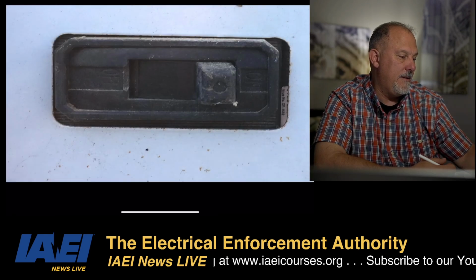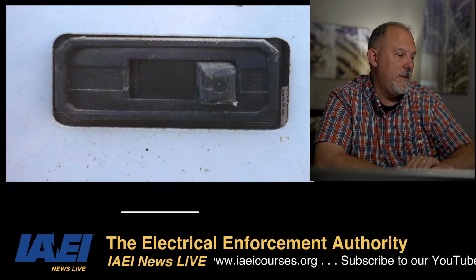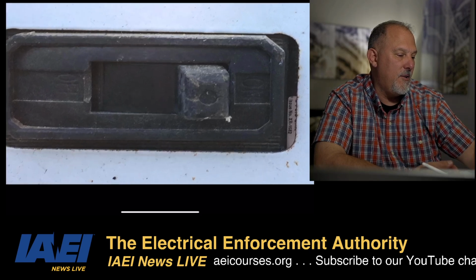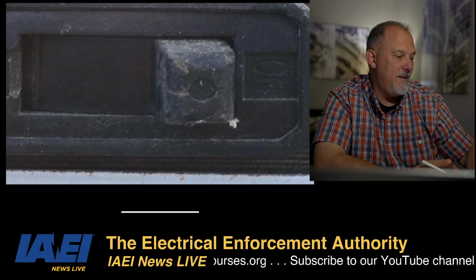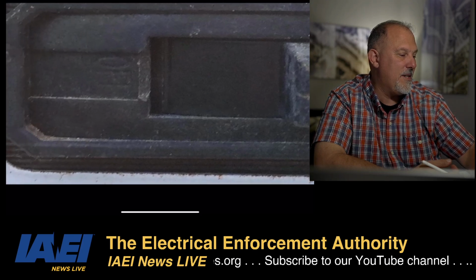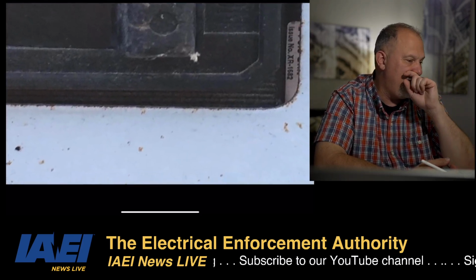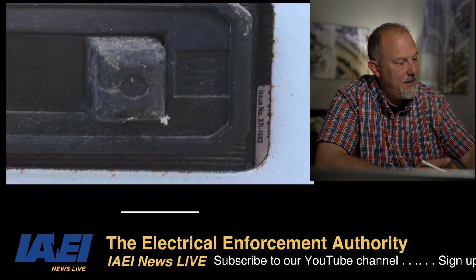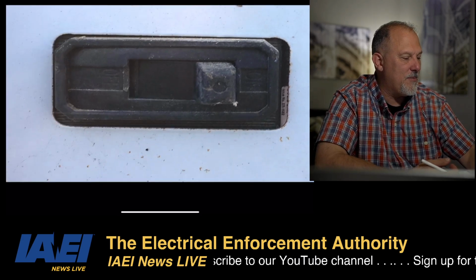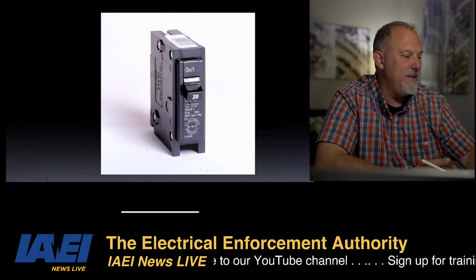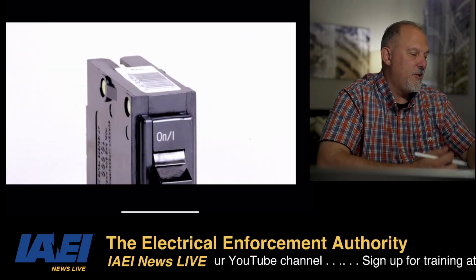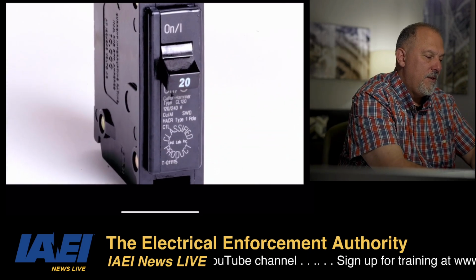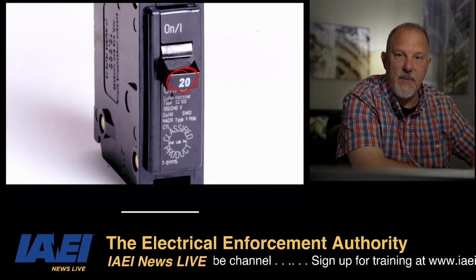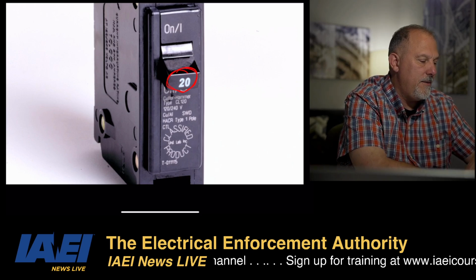All right. Well, look at this puppy. There's no marking on this at all. If there was a marking, I see the on-off. I see on-off, but I don't see much more of anything there. There's your 20 amps. So that's on the handle. That's going to be visible with the dead front on.